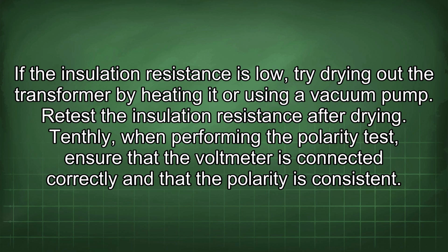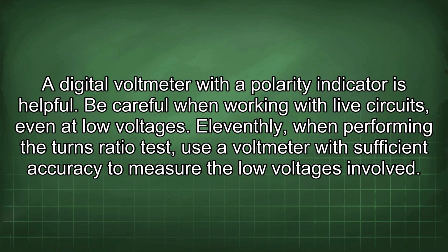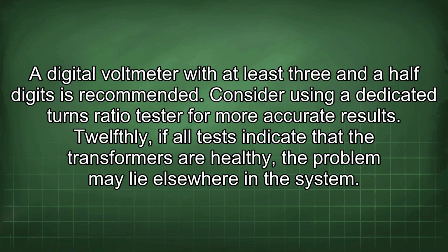Tenthly, when performing the polarity test, ensure that the voltmeter is connected correctly and that the polarity is consistent. A digital voltmeter with a polarity indicator is helpful. Be careful when working with live circuits, even at low voltages. 11thly, when performing the turns ratio test, use a voltmeter with sufficient accuracy to measure the low voltages involved. A digital voltmeter with at least 3.5 digits is recommended. Consider using a dedicated turns ratio tester for more accurate results.